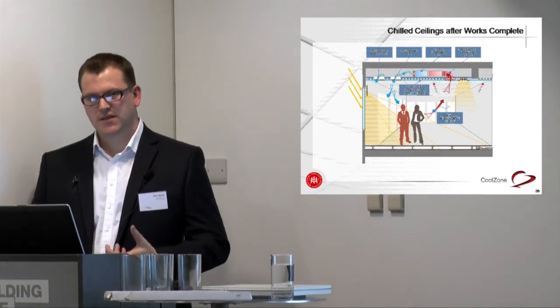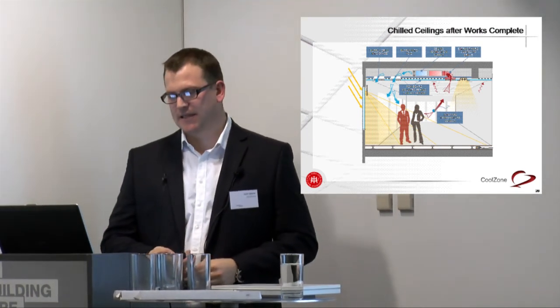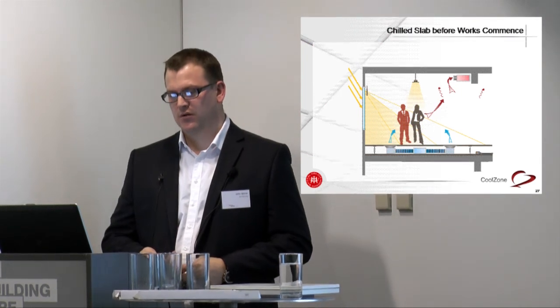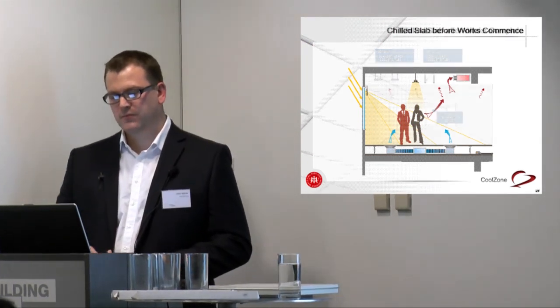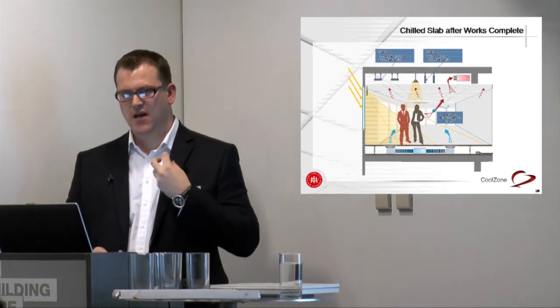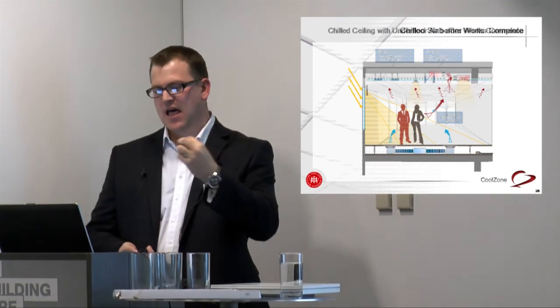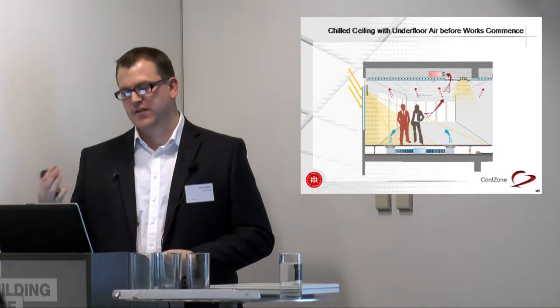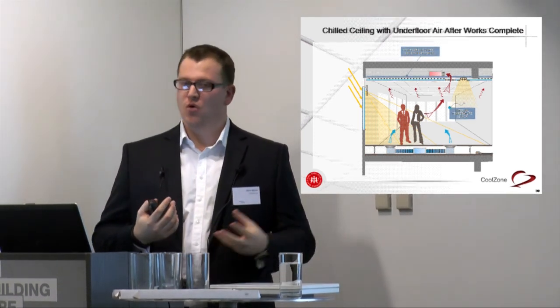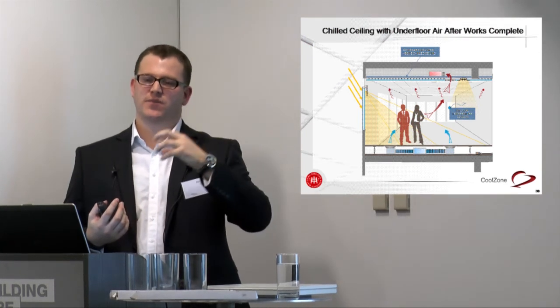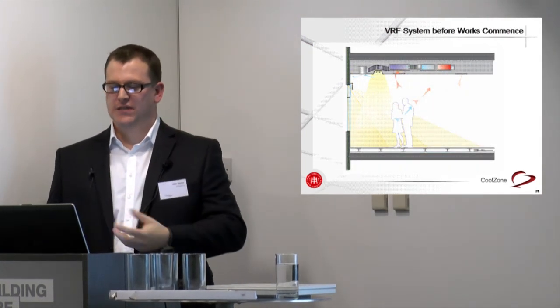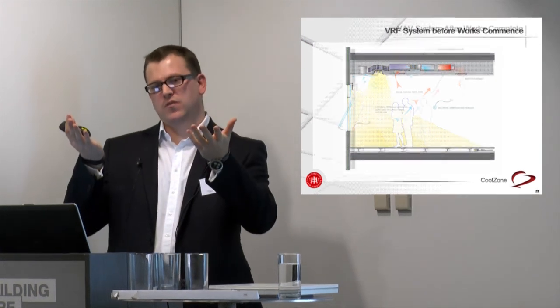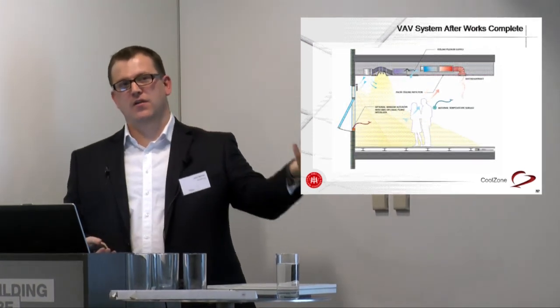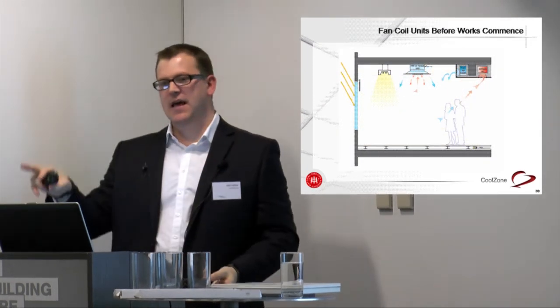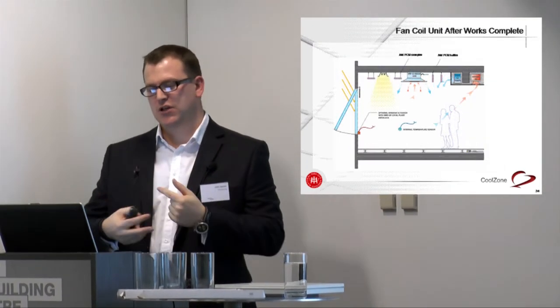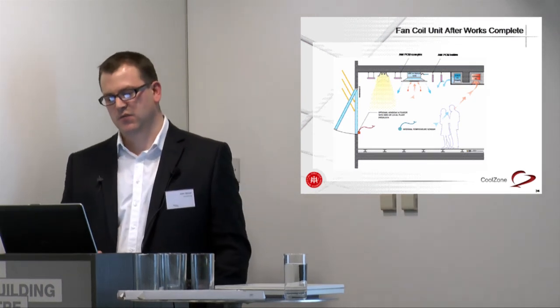These are some worked examples for different types of air handling systems and what you'd want to do. Essentially we want a ducted extract, to get that hot air out of the void. So either have a ducted air extract, or introduce ventilation into the void space to promote airflow, because the heat in the cool zone wants to rise through natural convection. If we can get airflow passing over the back of the tile, we can circulate that back into the room, get a better mix and some turbulence, which helps reset the tiles a bit quicker.